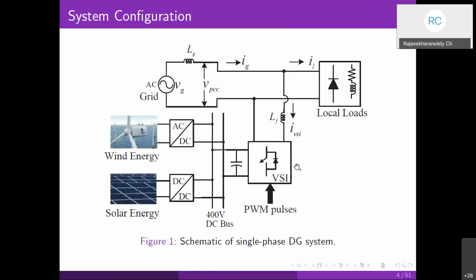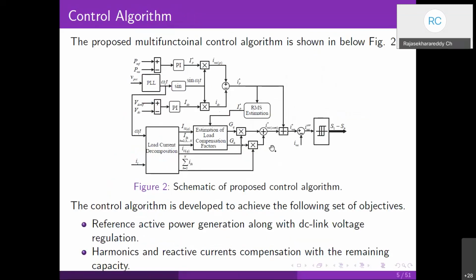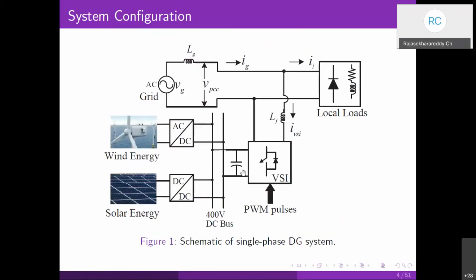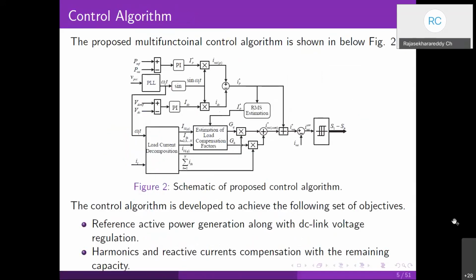So therefore we need to give priority for the active power generation first. Later we can give priority for either harmonic or reactive current compensation, based on the remaining current capacity of the voltage source inverter. If you look at the control structure for this system, this is the basic control structure. We are giving preference to the reference active power generation, assuming we know how much power is to be injected, and then we are using a PLL for synchronization.